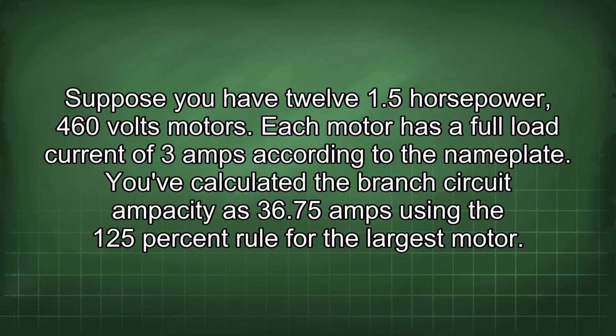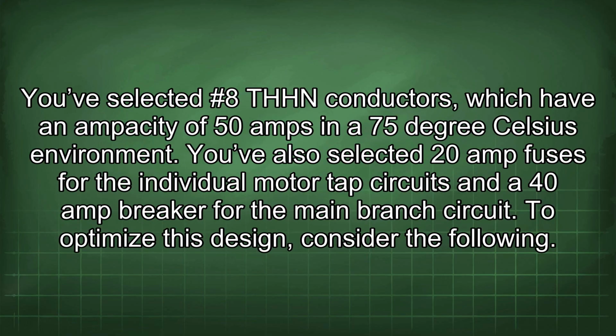Suppose you have 12 1.5 horsepower, 460 volts motors. Each motor has a full load current of 3 amps according to the nameplate. You've calculated the branch circuit ampacity as 36.75 amps using the 125% rule for the largest motor. You've selected #8 THHN conductors, which have an ampacity of 50 amps in a 75°C environment. You've also selected 20 amp fuses for the individual motor tap circuits and a 40 amp breaker for the main branch circuit. To optimize this design, consider the following.